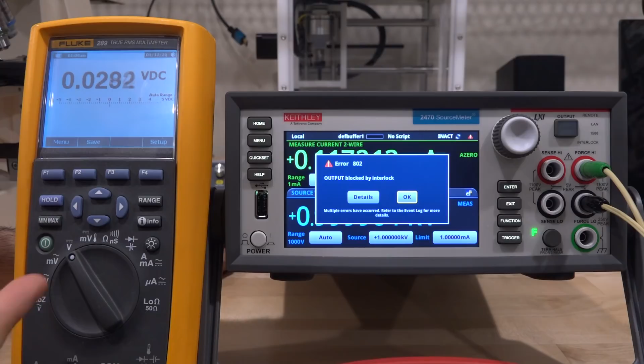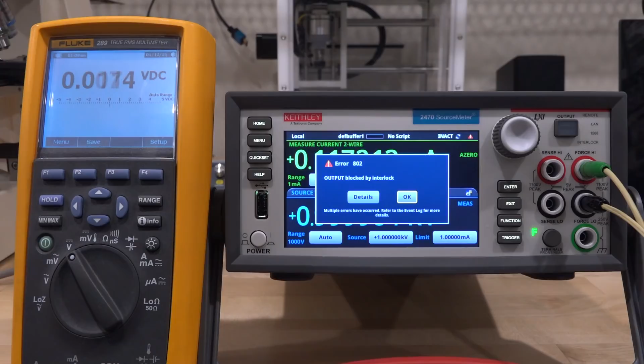Remember that this instrument has a 10 megohm input impedance, the Fluke. This means it's not being discharged through the Fluke, but rather handled by the instrument itself, and you get a warning telling you the interlock has been tripped. This is really important, especially in high voltage test setups.